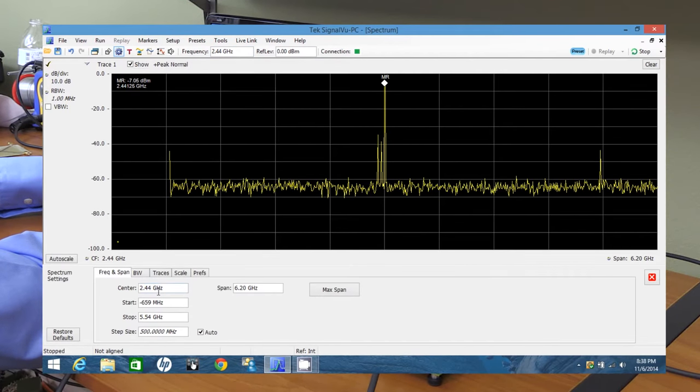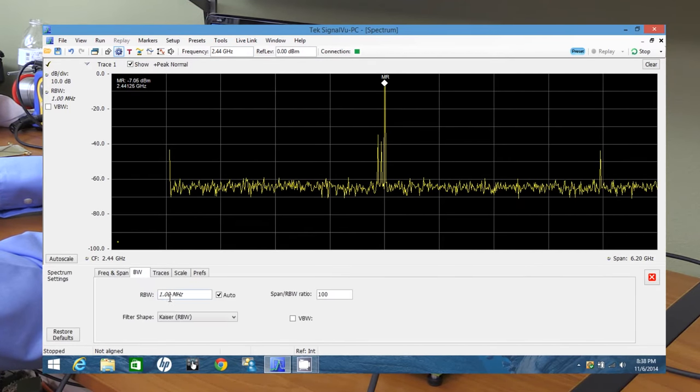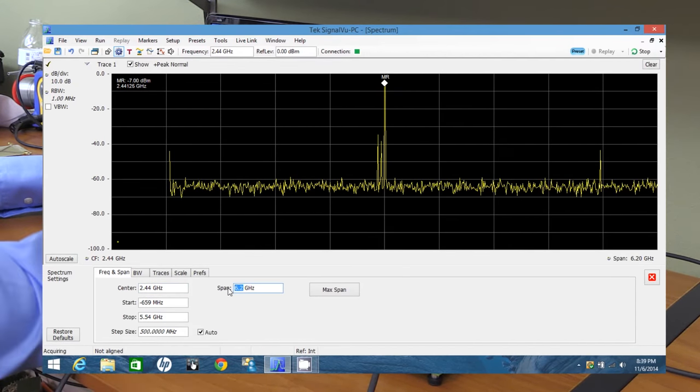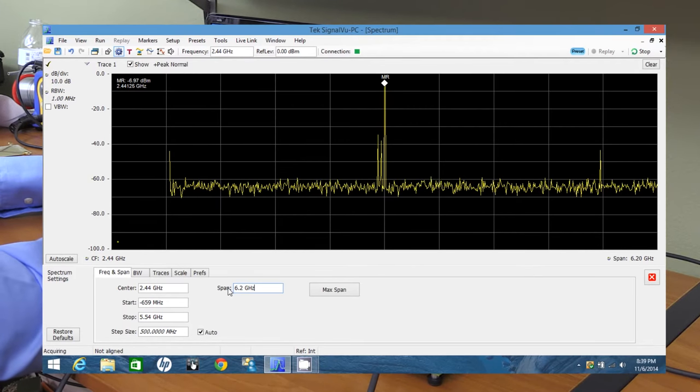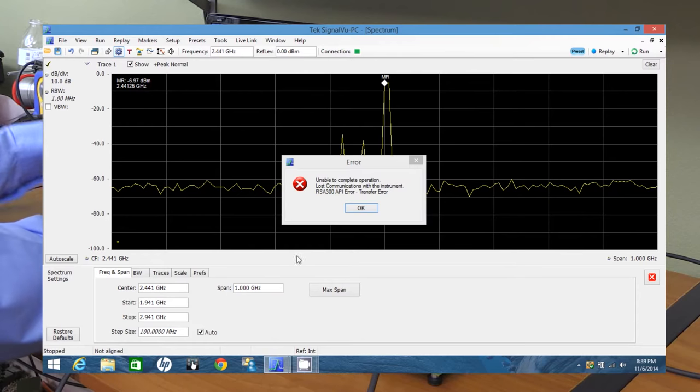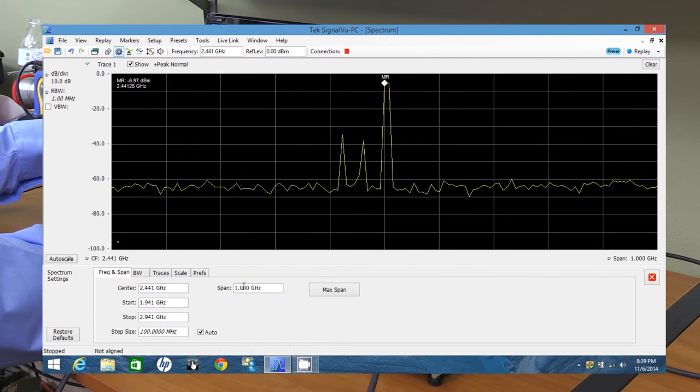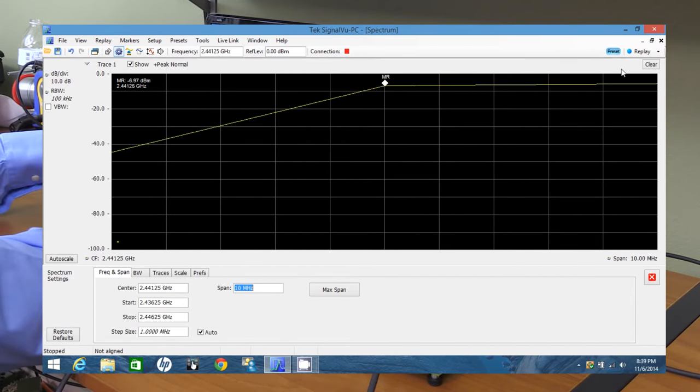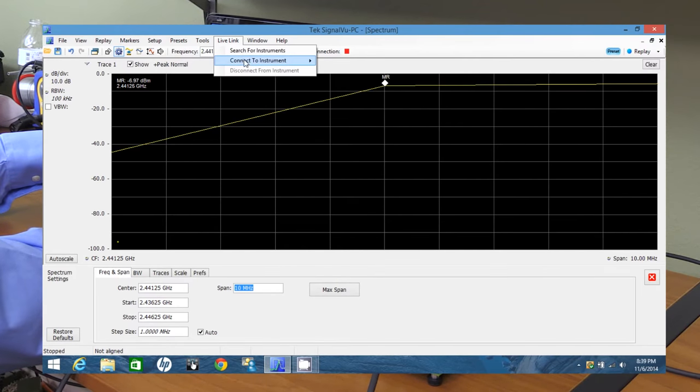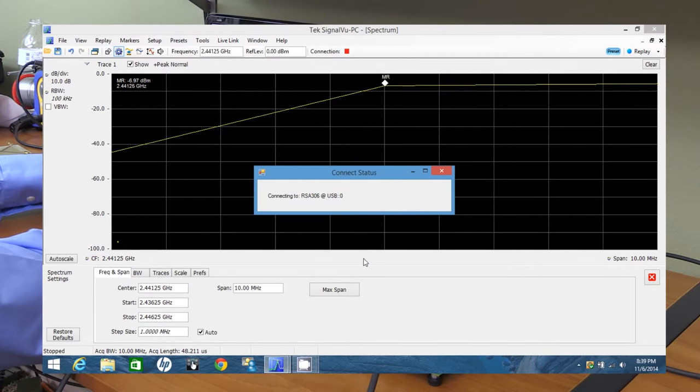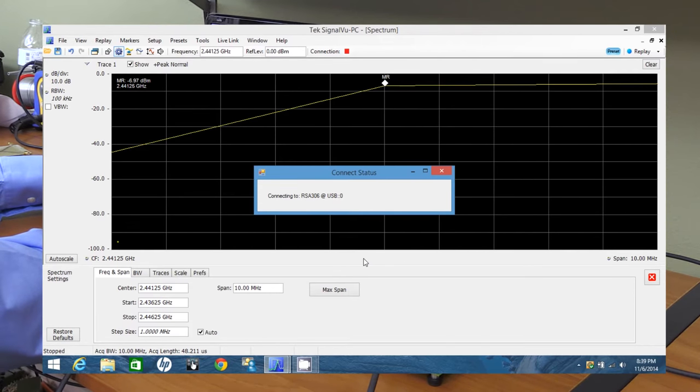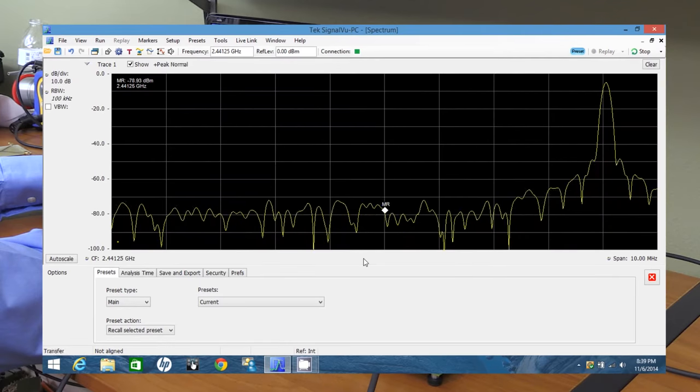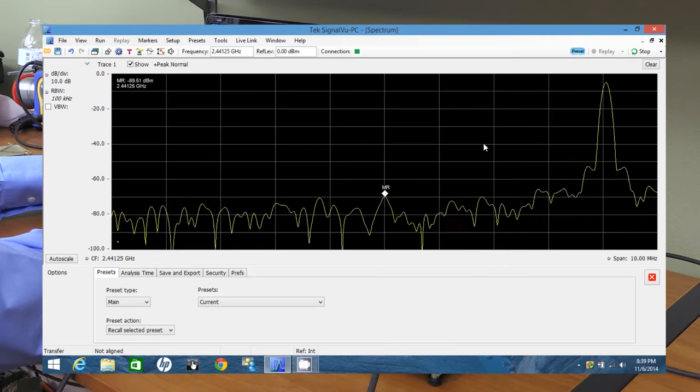Now, if we go into settings, we can set up our resolution bandwidth. And here's our span, which is currently set to 6.2 gigahertz. We're going to reduce that to, let's make that 10 megahertz. Something broke. Let's try it again. 10 megahertz. It lost the connection. So let's reestablish our connection. I don't know why that broke. It's the first time that happened to me, but we can just easily reconnect.